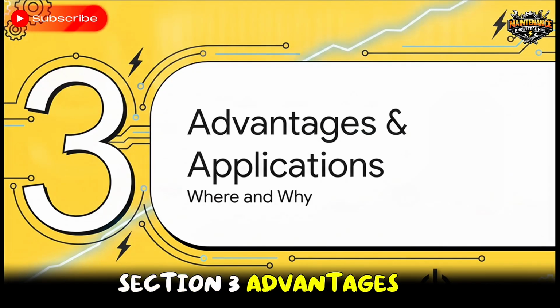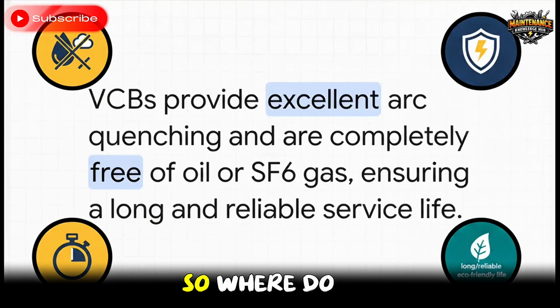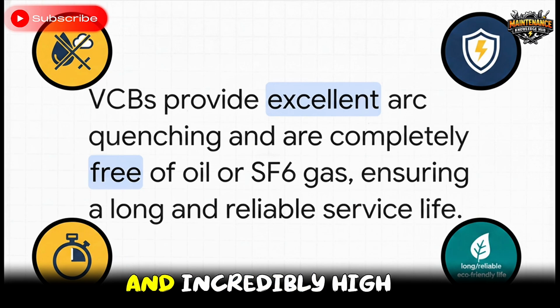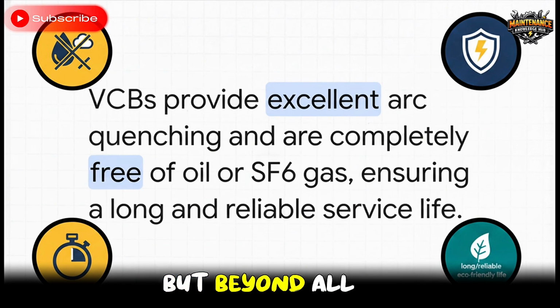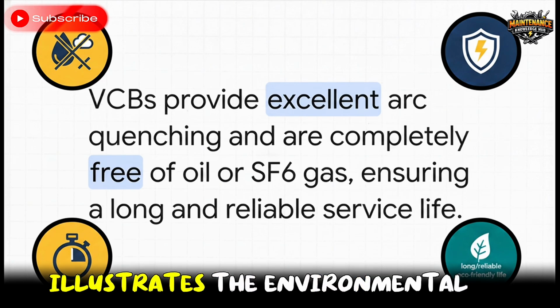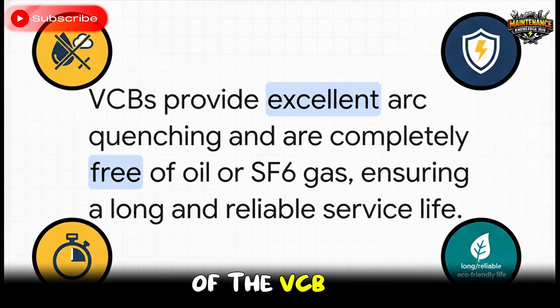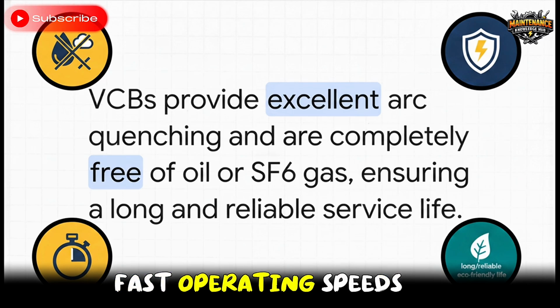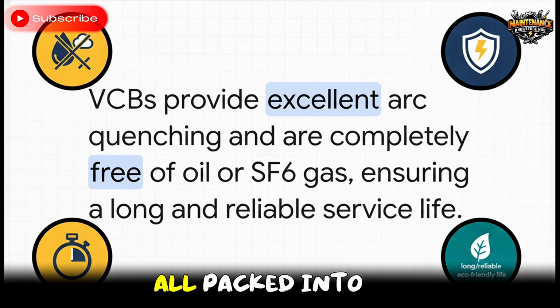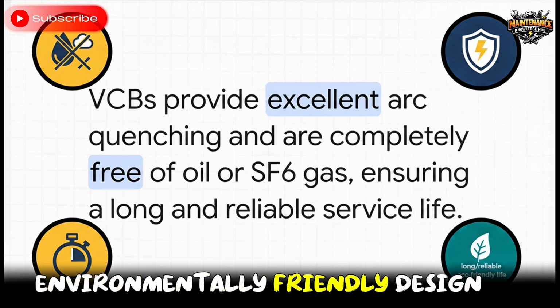Section 3. Advantages and applications. So, where do we actually use this technology, and why is it the go-to choice? Well, the value proposition of a VCB is just massive. They offer excellent arc quenching, a super long service life, and incredibly high dielectric strength. But beyond all of that, they are completely 100% free of oil or SF6 gas. And this brilliantly illustrates the environmental and operational edge of the VCB. You're getting blindingly fast operating speeds suitable for frequent switching, all packed into a really compact, environmentally friendly design.